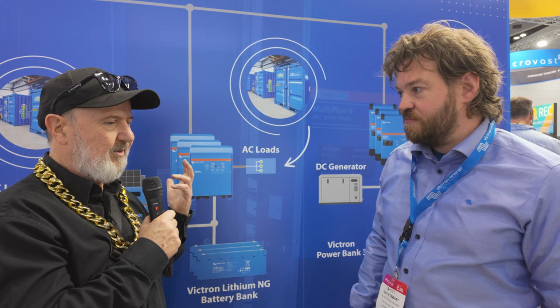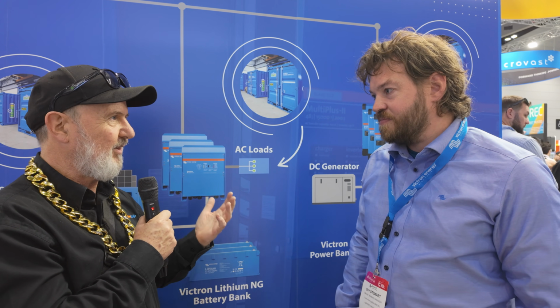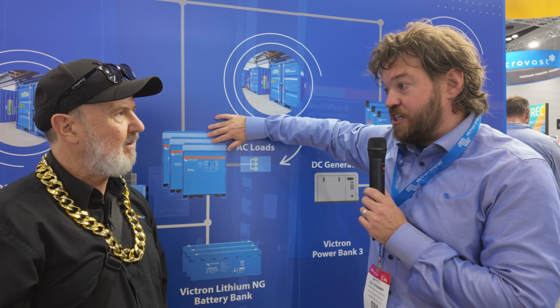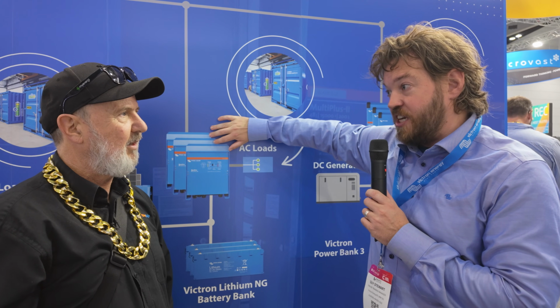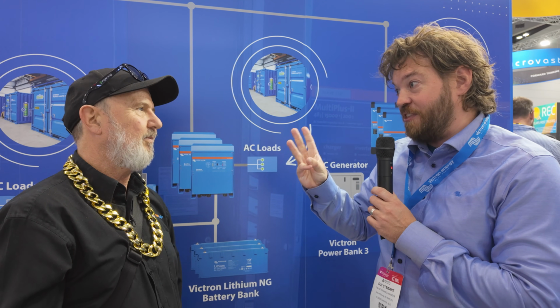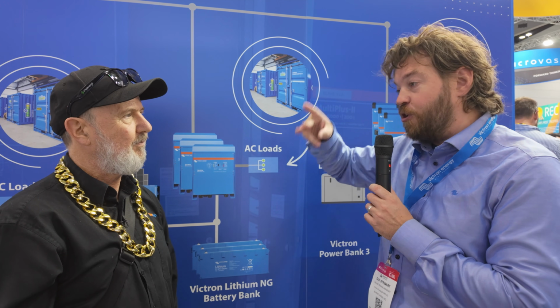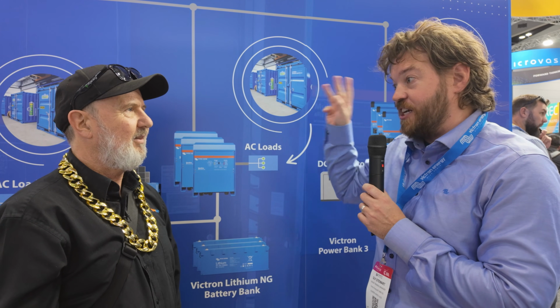Since the Quattros are single phase, how do you synchronize multi-phase when there's not a VE bus? For each individual cluster, if you want a three-phase system, you'll still need to synchronize the three Quattros in that individual system. If you want a three-phase system, you'll need three connected via the bus. That'll form the backbone of the three-phase microgrid.